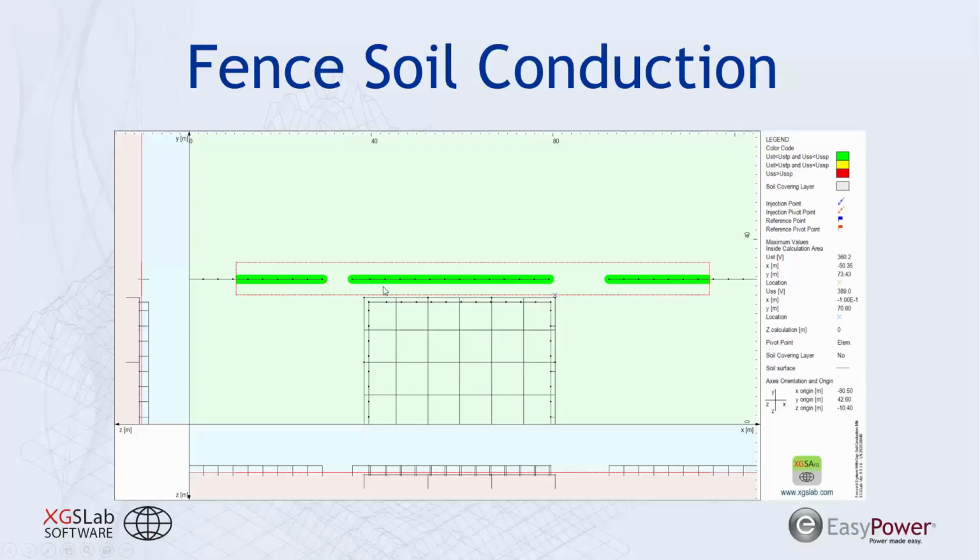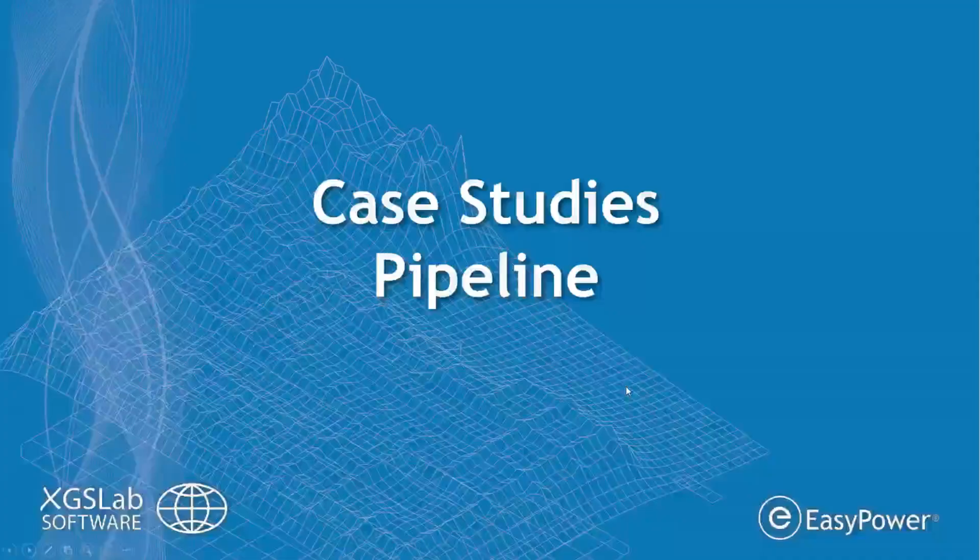in multiple locations. So in this central fence section where we're still using that steel fence, we have the soil at the person's feet is at the same potential or relatively close potential to the fence itself. And we can see that on the left and right hand side.